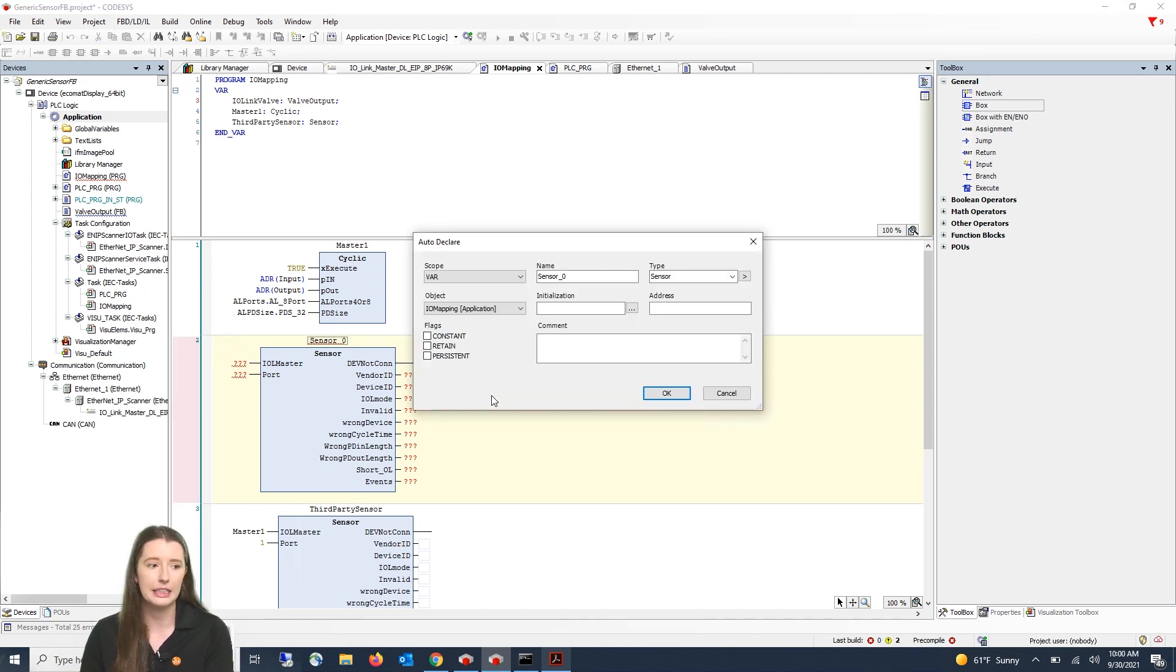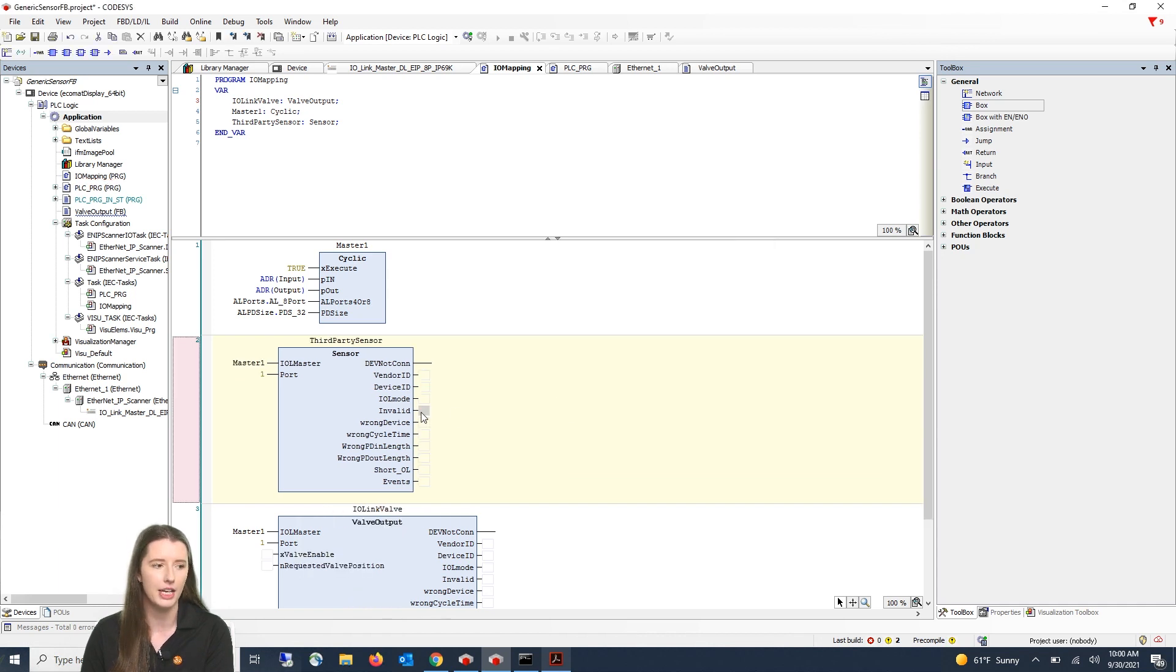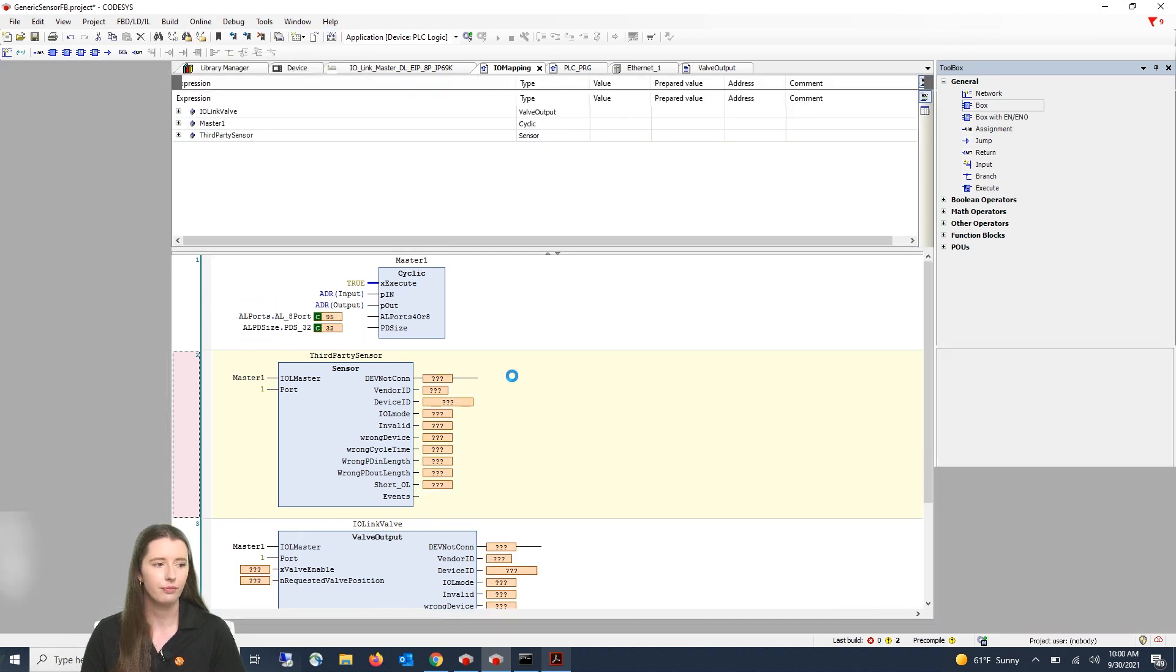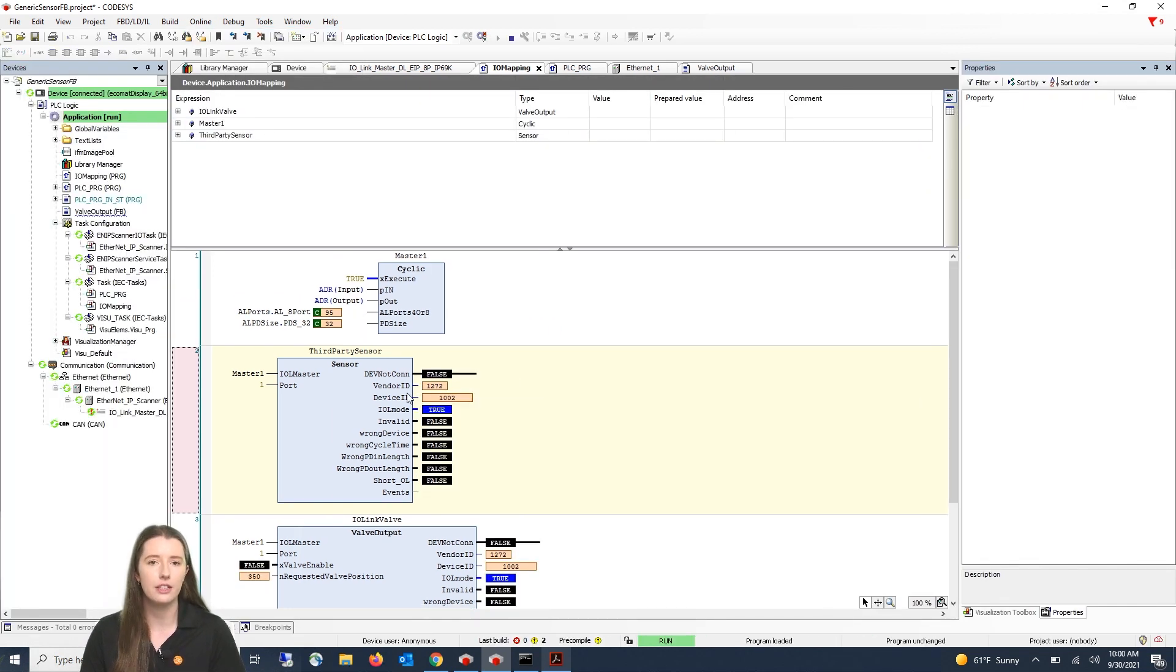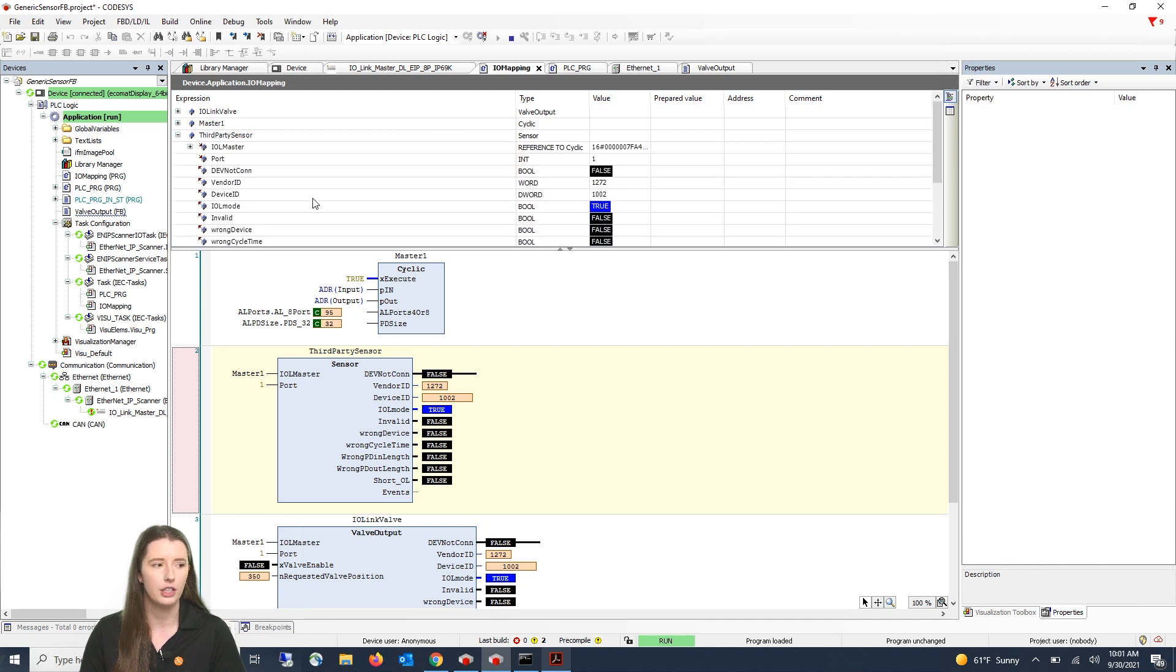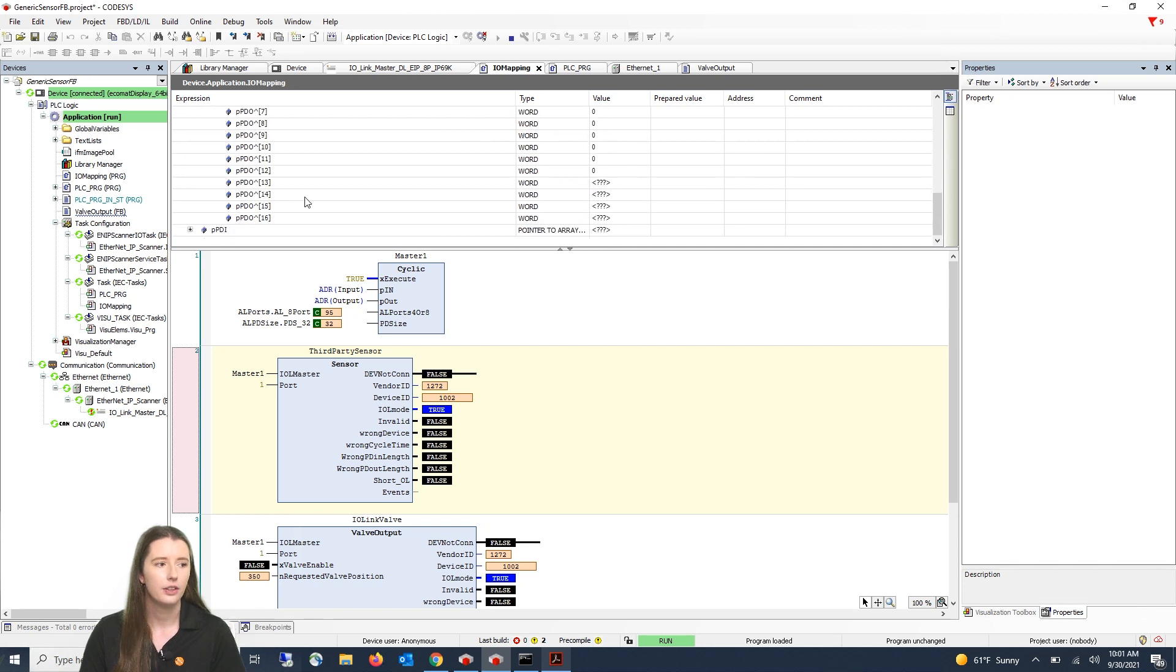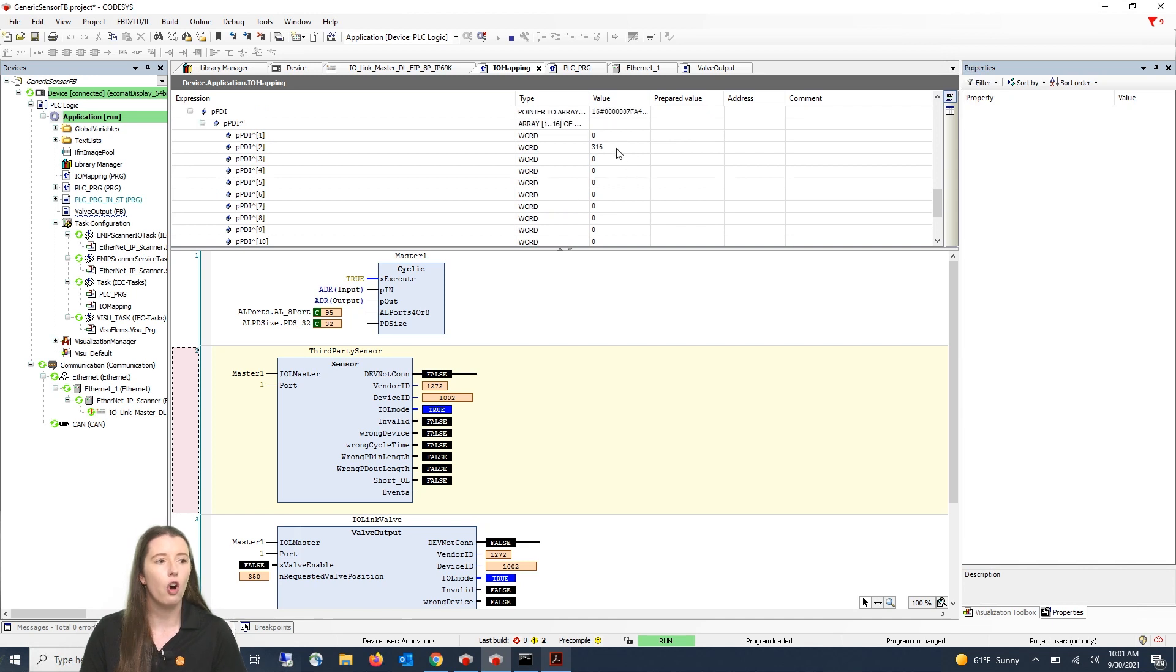I'm now going to delete this rung because we already have this function block created and if you go online and log in you can see the vendor ID and device ID of your third-party device being pulled in. If you go up above and drop down your third-party sensor information and go down to your process data output array as well as your process data input array you will see the raw values of your third-party device being pulled in.